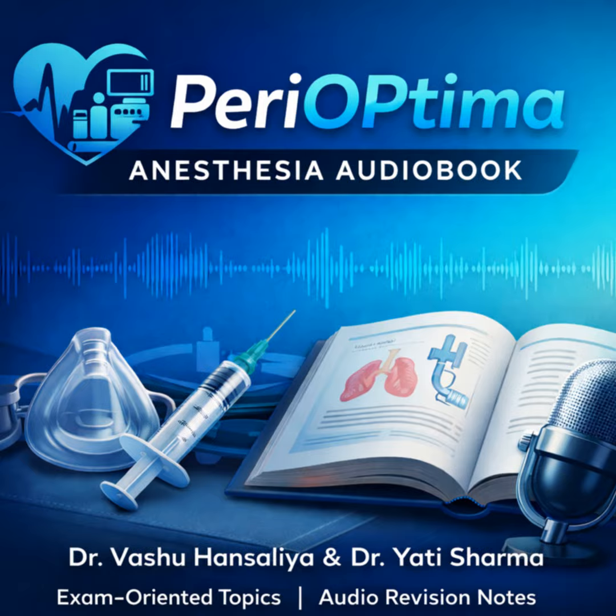And how does that change fundamentally when we switch to controlled ventilation? The change is all about the APL valve and the pressure dynamics. When the anesthetist is controlling ventilation, either manually with the bag or mechanically with the ventilator, the dynamic shifts completely. It does. On inspiration, the anesthetist compresses the reservoir bag, or the ventilator drives the breath. Now, to deliver that positive pressure, the APL valve has to be closed or switched to ventilator mode. The gas is then forced through the inspiratory limb, and that inflates the lungs.